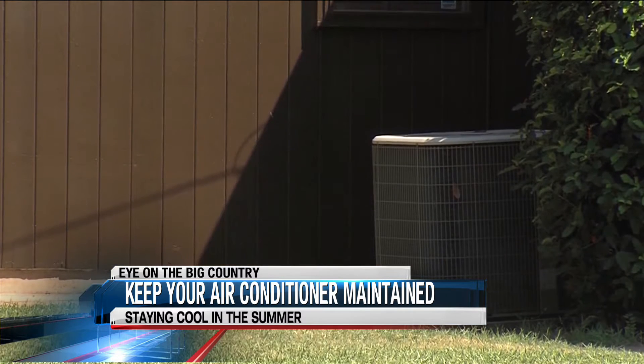If you prefer a DIY service cleaning, here's how. Find the power source to that outdoor unit, kill the power to that outdoor unit, and get a garden hose with a high-pressure nozzle. Go in an up-and-down motion, flushing the water up and down through that coil to get all that debris and grass and pet hair and stuff off that outdoor coil.